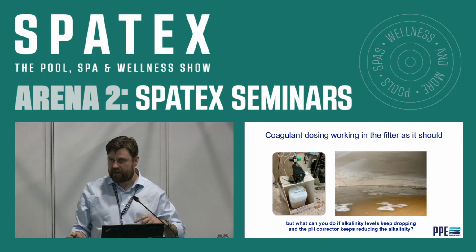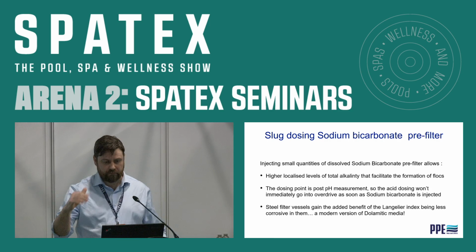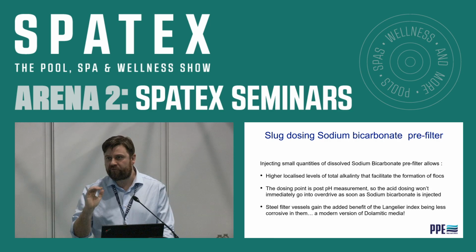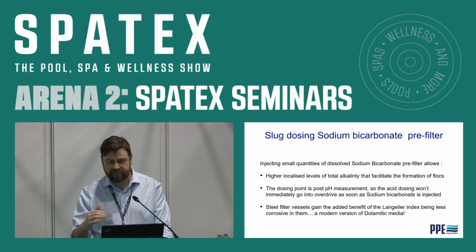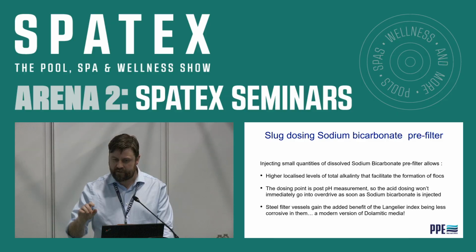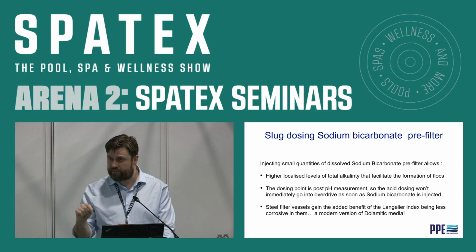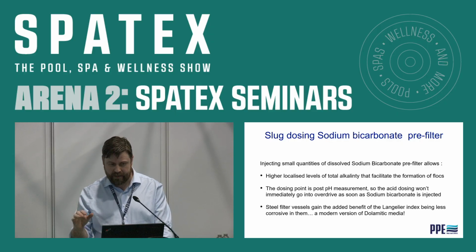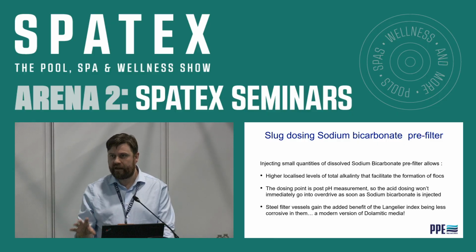If you're really struggling and you're still dosing it by hand, I would recommend still putting it in, but really, really minute amounts continuously, really slowly. I would always say, if you can, dissolve it in a tank, pump it in the same way that we pump in other chemicals, almost like the way we do sodium bisulfate, but our injection point's got to be quite key, okay? Where is it most important to have highest alkalinity levels?